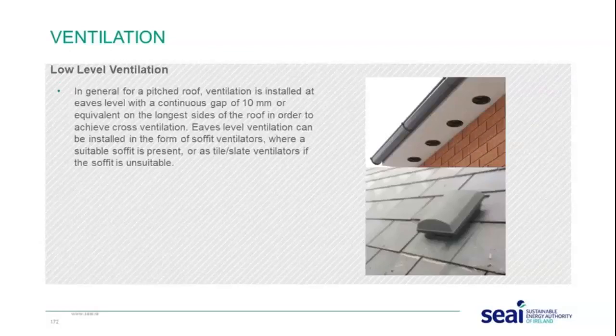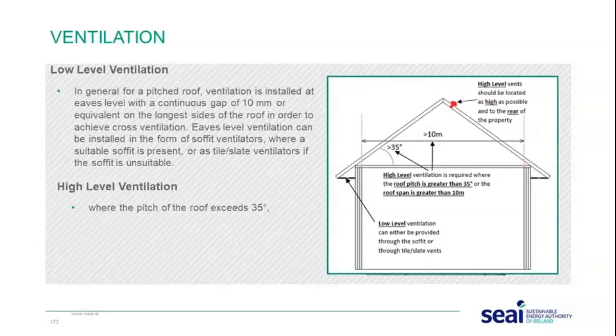This provides good cross ventilation and avoids creating pockets of stagnant air. Ventilation in the roof space should be checked. For low level ventilation on a pitched roof, ventilation is installed at eaves level with a continuous gap of 10 millimetres or equivalent on the longest side of the roof. Eaves level ventilation can be installed as soffit ventilators or as tile/slate ventilators if the soffit is unsuitable.